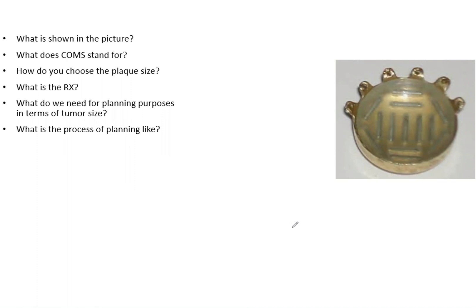What do we need for planning purposes in terms of tumor size, and what is the planning process like? This is a typical eye plaque. COMS - I won't write it all out - stands for Collaborative Ocular Melanoma Study. COMS defines plaques, including plaque sizes, rules and regulations, the RX, dose calculations for verification and second checks, and reporting for eye I-125 treatments.